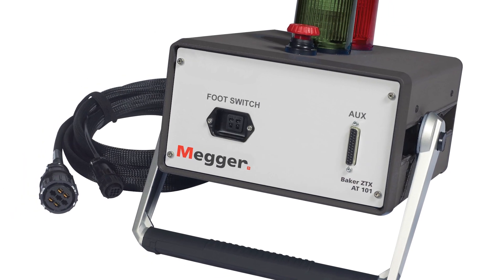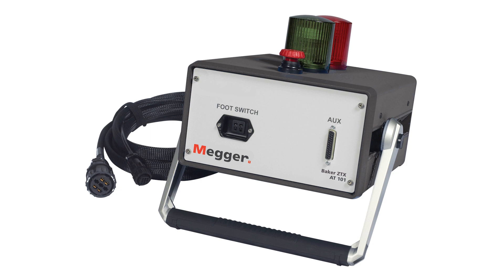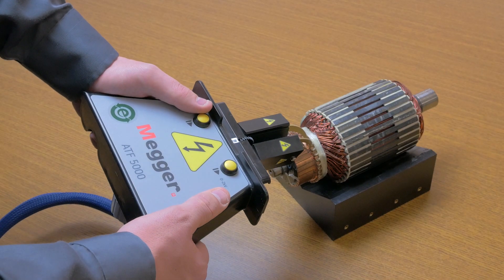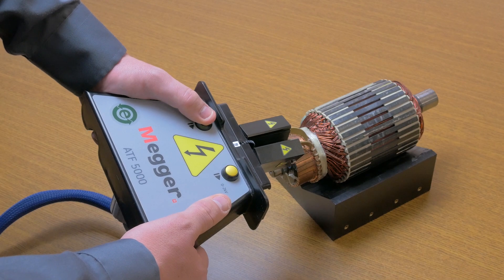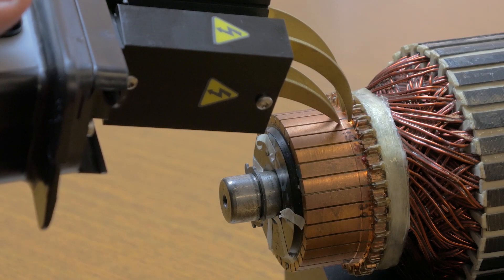DC motor armatures can also be tested using the Baker ZTX adapter with a Baker static motor analyzer. The ZTX lowers the surge voltage while increasing the current. This allows bar-to-bar testing of the armature with excellent fault location.